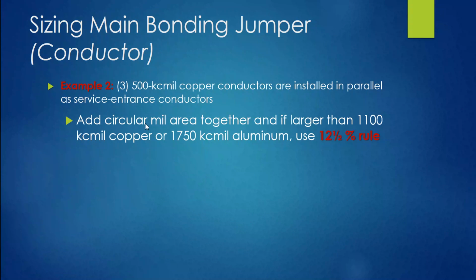So you add the circular mil area together, and if larger than 1100 kcmil copper or 1750 aluminum, you've got to use a 12.5% rule. Well, in our case, we did. We have 3 sets, so you take the largest ungrounded service conductor in each raceway. And so you don't add them all up. In this case, you don't add the 3, the 3, and the 3. You're just taking the 1 from each raceway and adding them together. So in this case, it's 500, 500, and 500 because we have 3 parallel sets of 500 kcmil in separate raceways. And so 3 times 500 is 1500 kcmil.